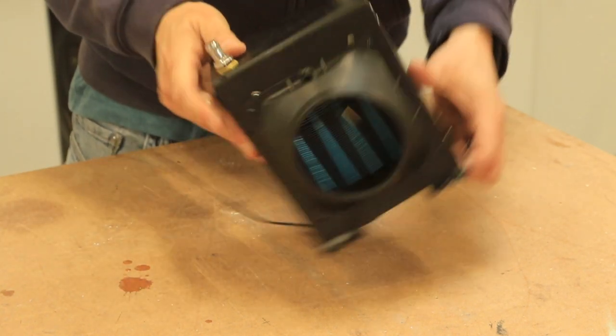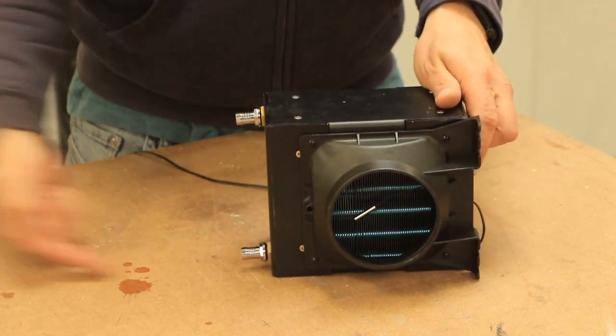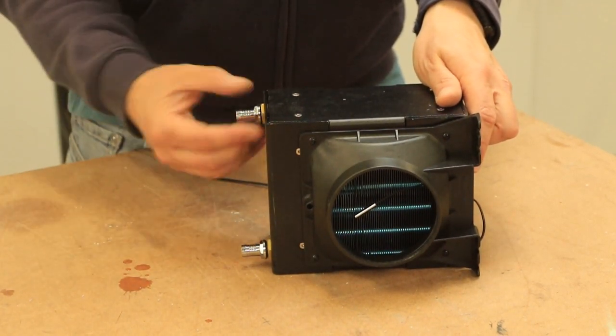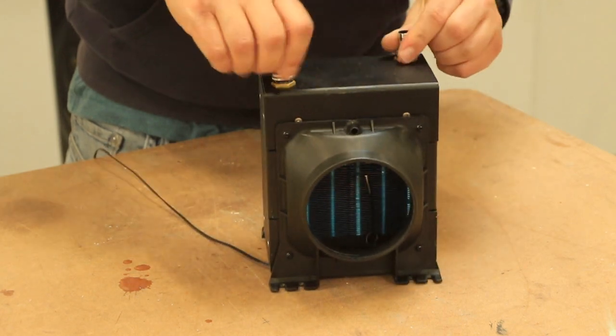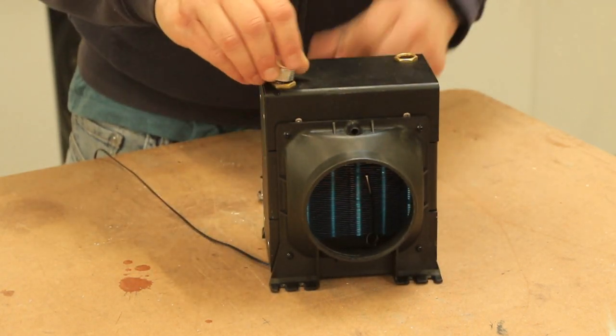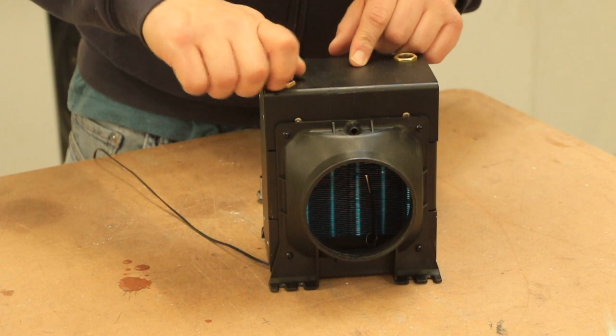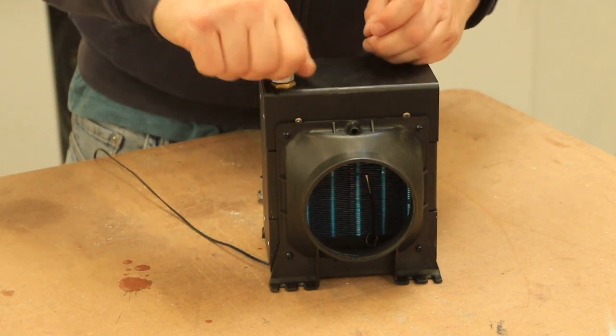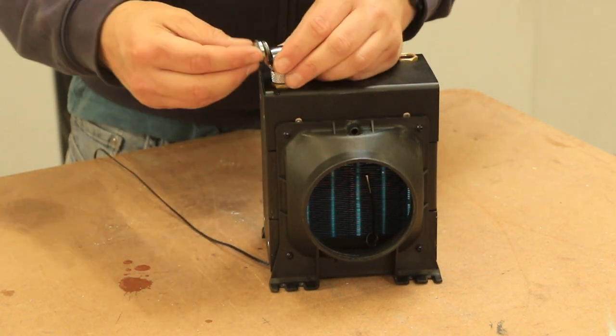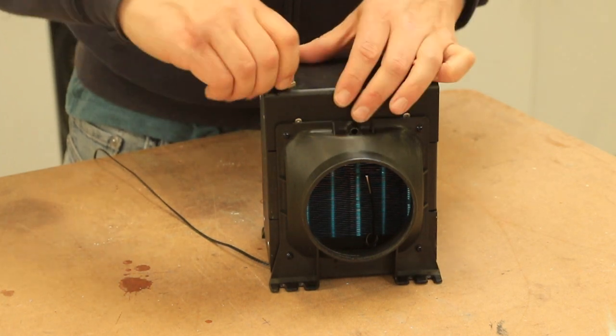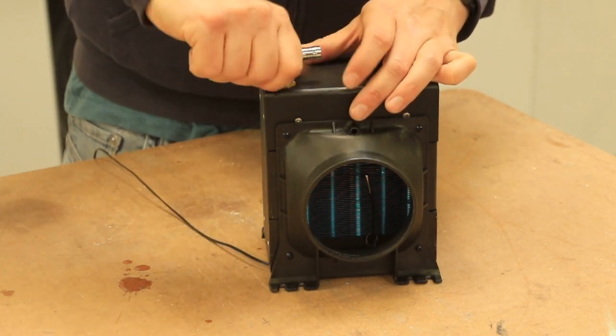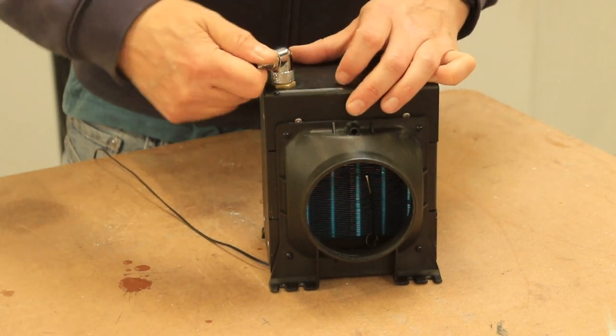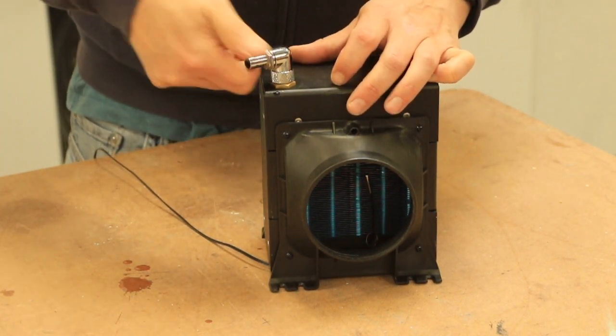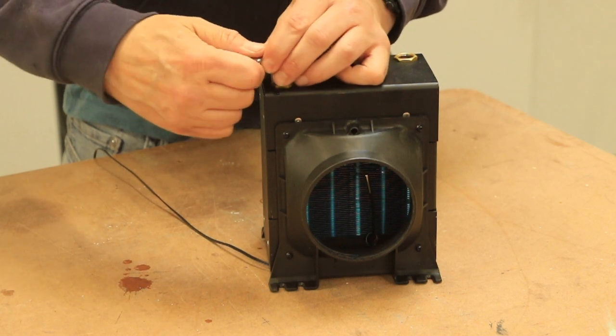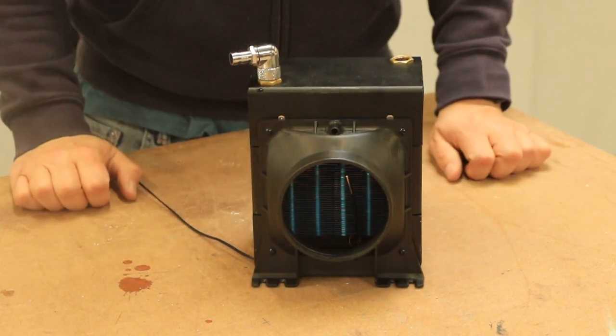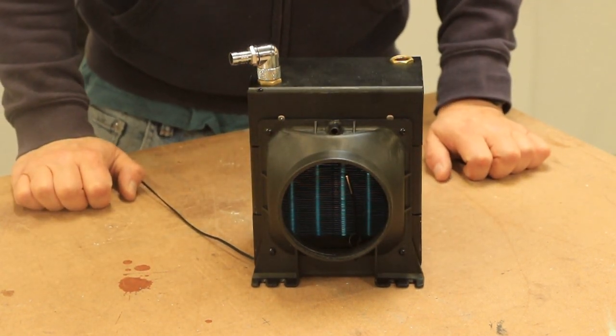So for example, if you're mounting this on its side, you might think that that's going to be easier to come straight in. If you wanted to have this on the top, you might want to have these little elbows, but you just screw the elbows in, screw the elbows in, screw the barb fitting in, and that's it. Again, you really don't need to go too tight with these. Hand tight is absolutely fine. And again, same with that one, just hand tight. The washer really compresses and gives that a good seal. So that's the heat exchanger all ready to go.